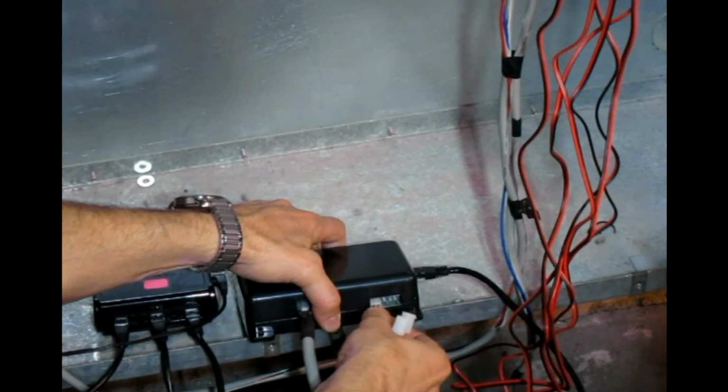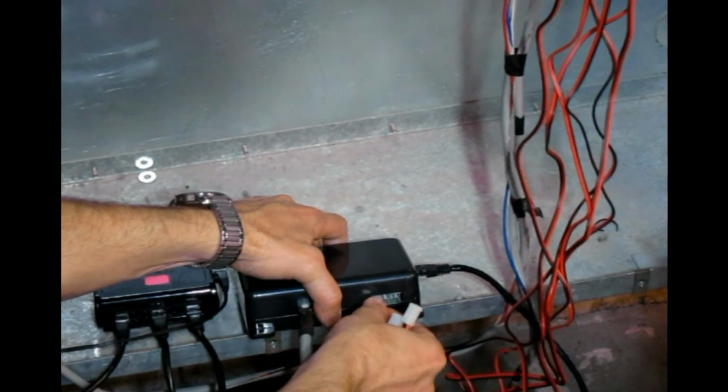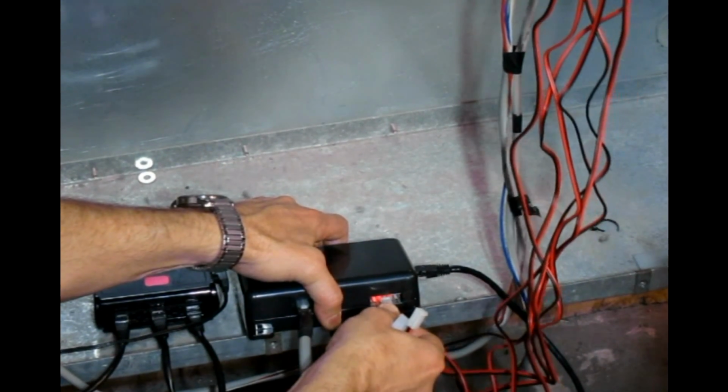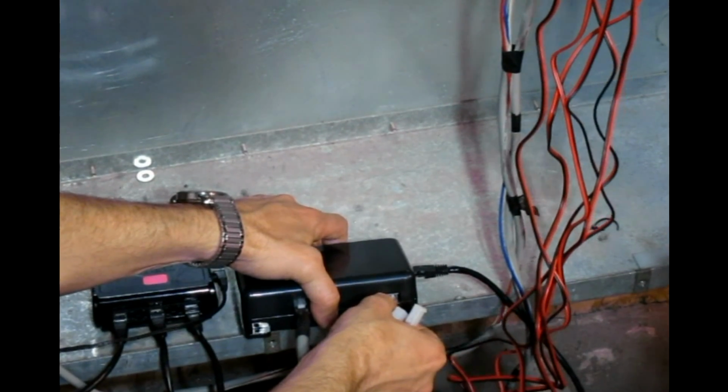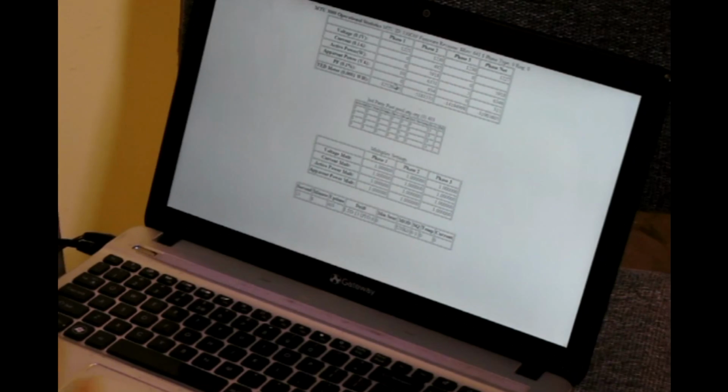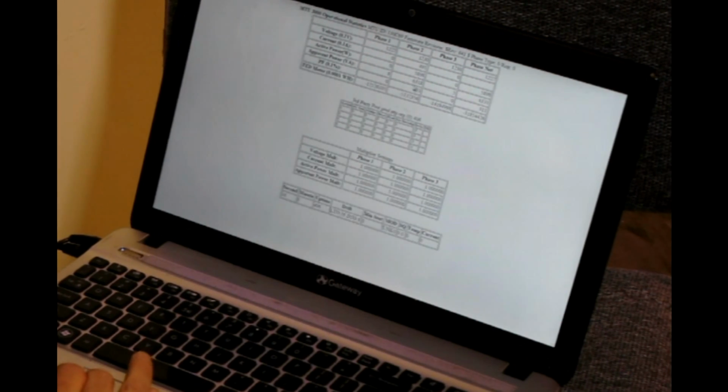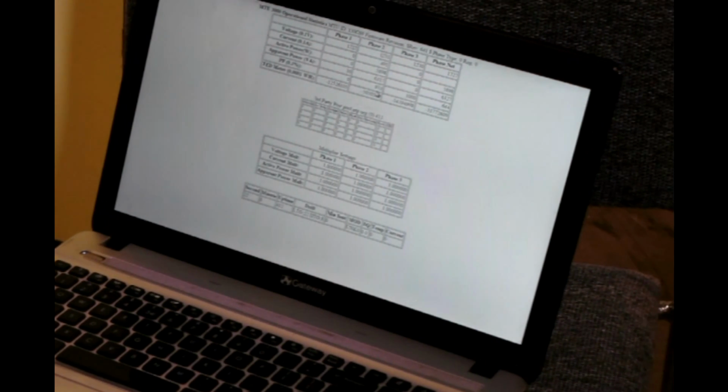And I'm going to take the connector that's in the A phase, and I'm just going to move it to the B phase and see what I see there. Now my active power went positive, as you can see, 5918, and my power factor is at 93%, which is typical. Okay, so I'm pretty sure that's the B phase.